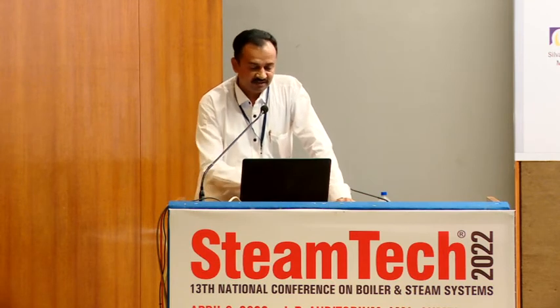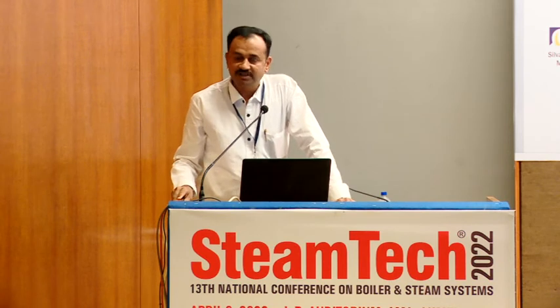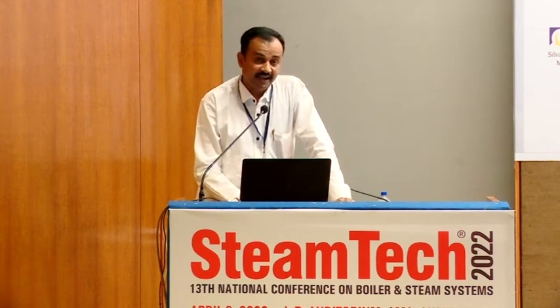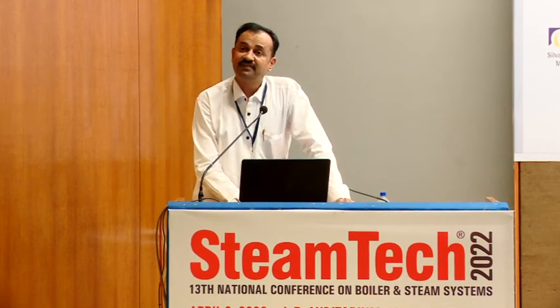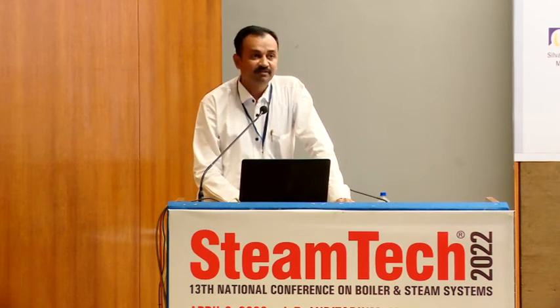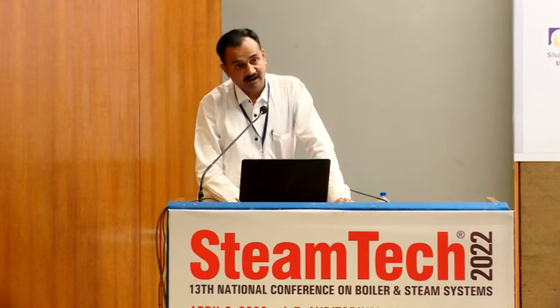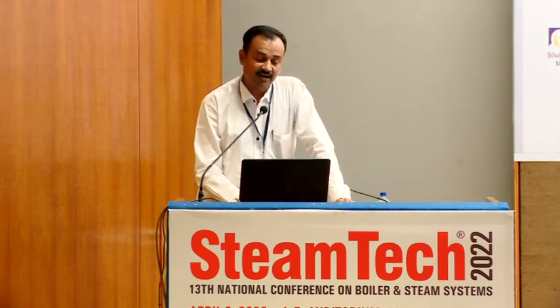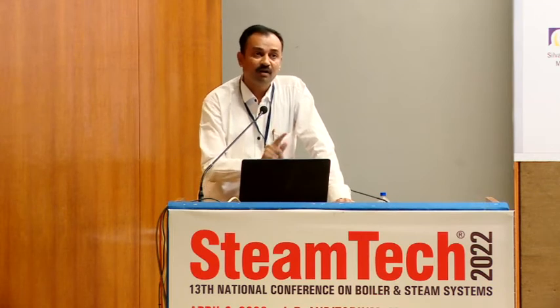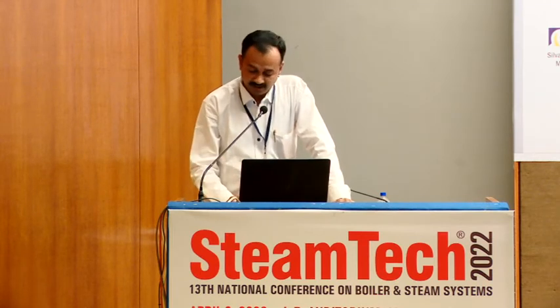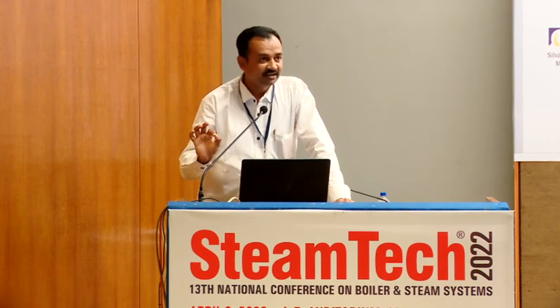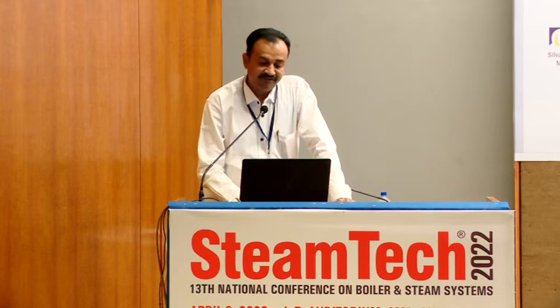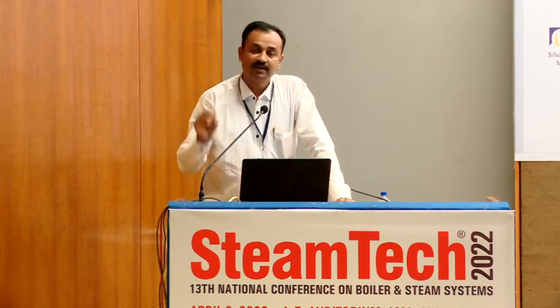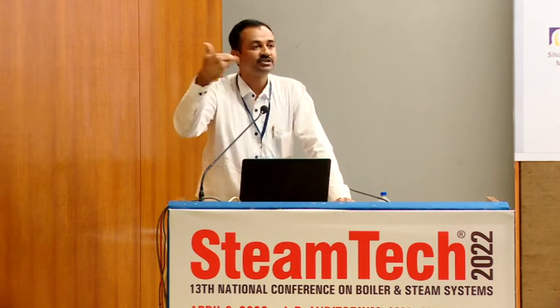How? You can see that during the pandemic time, the user wanted to start the boiler, a solid fuel boiler, and what we identified is that he cannot do any mishap. So we took the permissive feedback so that his ID fan starts only when the drum level is within the limit and the draft pressure is within the limit. Again, after the ID fan started, the FD fan should start only when all the combustion parameters or permissions are within the limit. The PA fan should start when the ID and FD are running and all the safety interlocks are within the limit, and the feeder should start when all the blowers are running and the combustion parameters are within the limit. This feedback we took as acknowledgement, and we helped him to start the boiler within the safe limit.